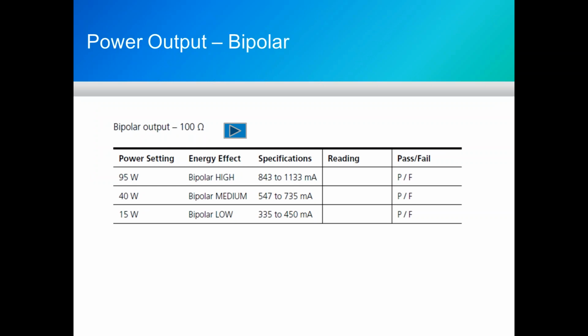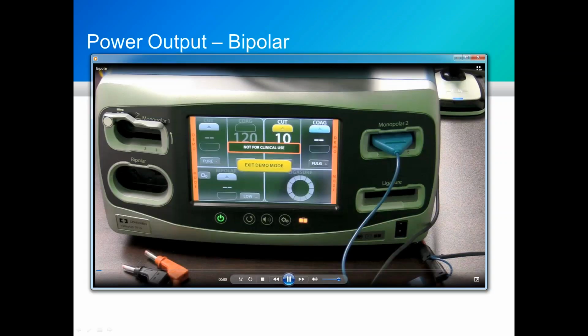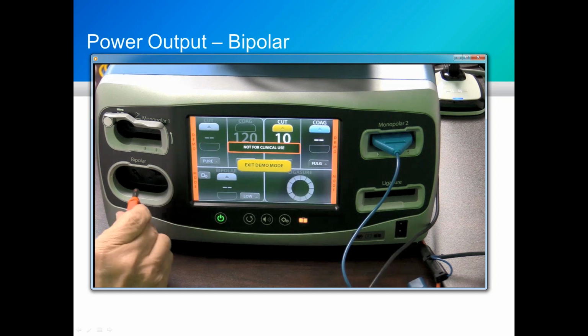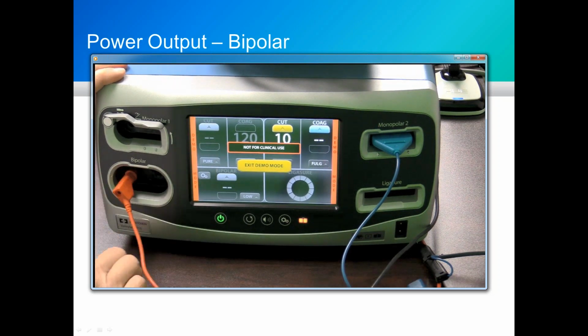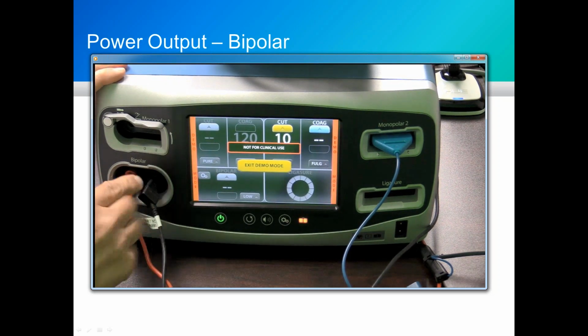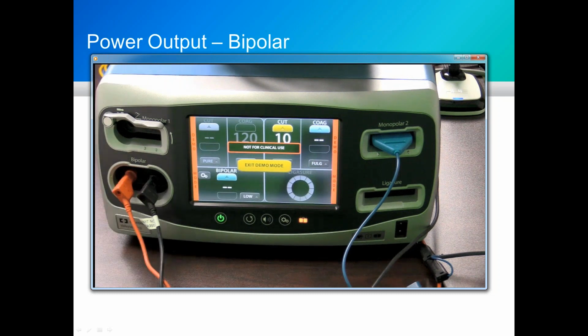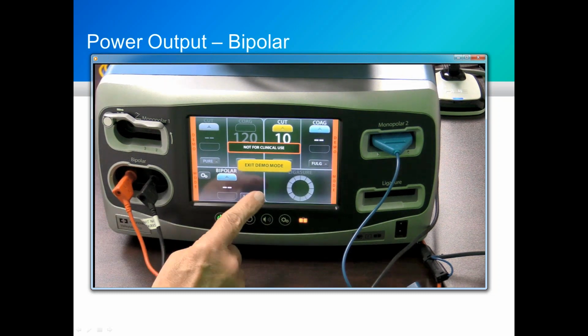So for bipolar output, here are the tests that we need to perform: low, medium, high. So we're going to go now and do this demonstration. Notice again that there are 2 micro switches now. So when you're using your test leads, be sure that the leads are contacting those micro switches, otherwise the port will not be energized.